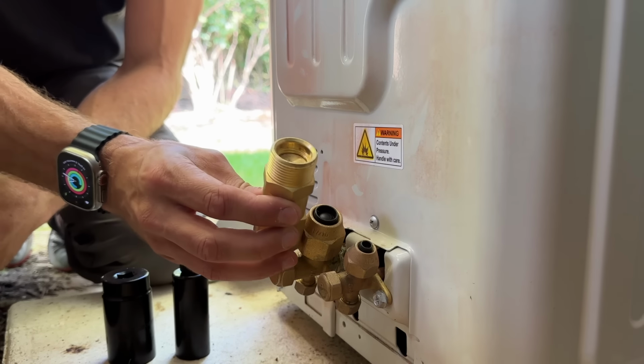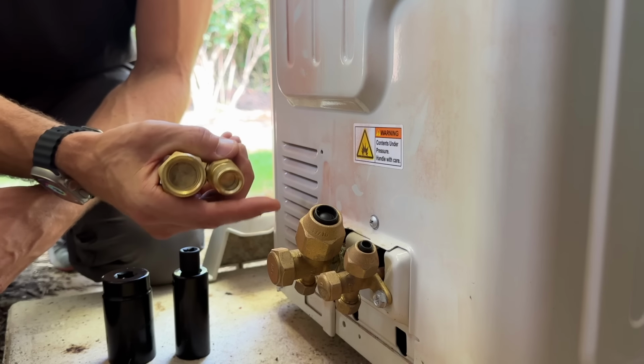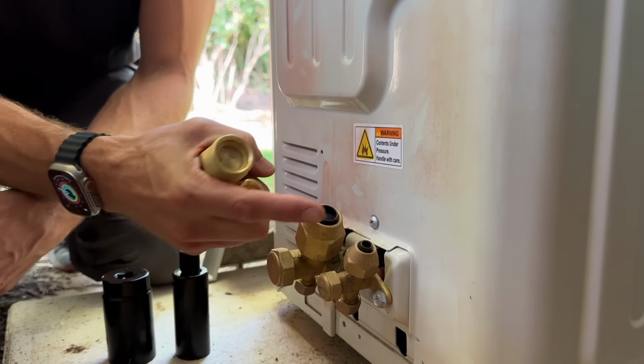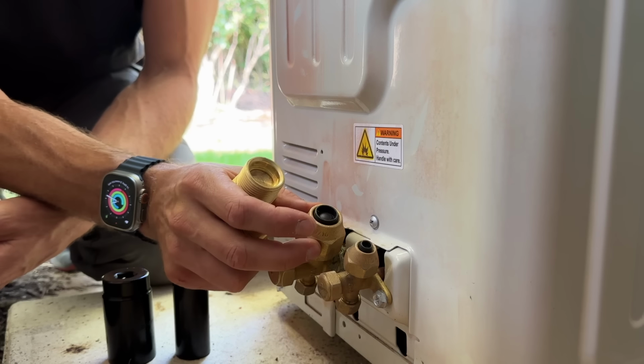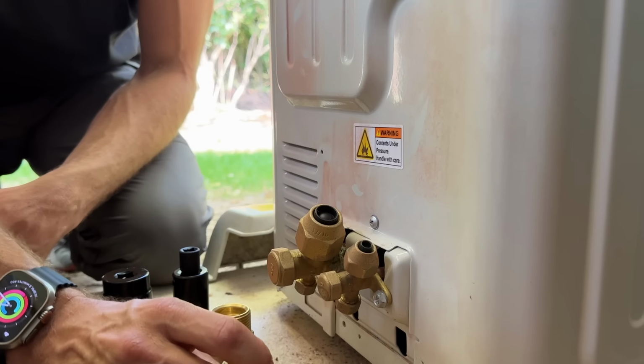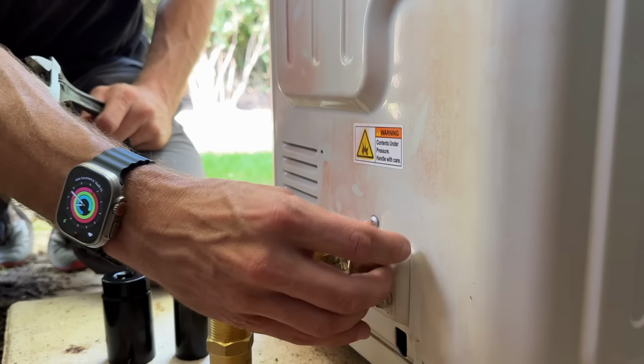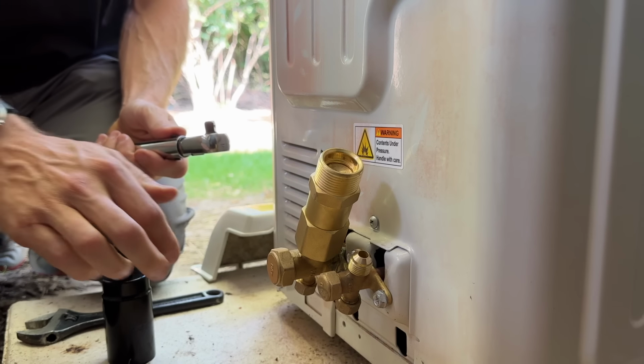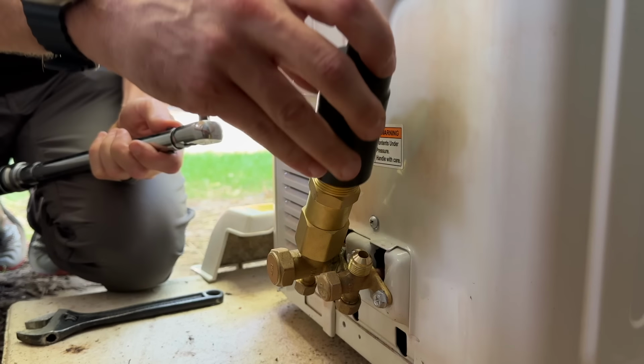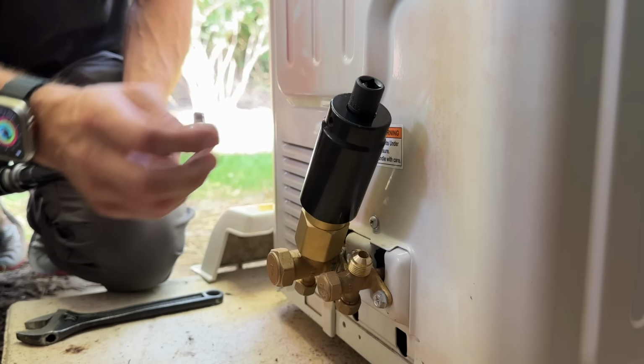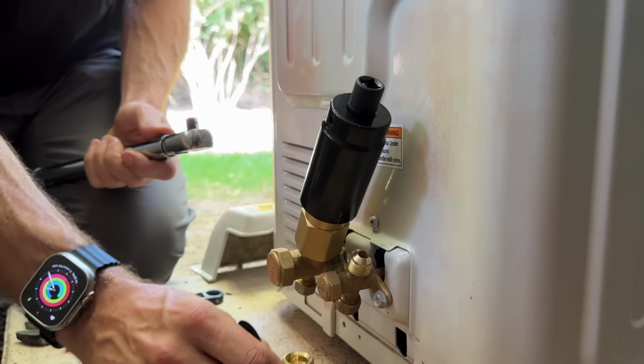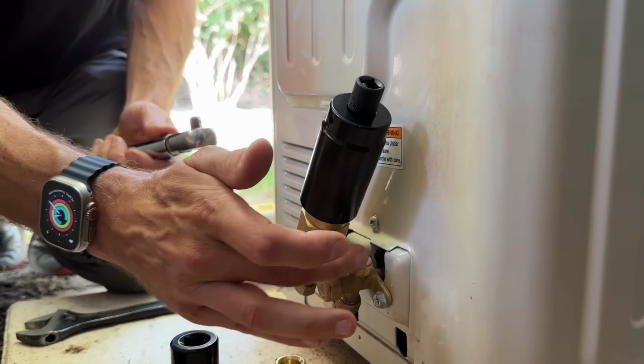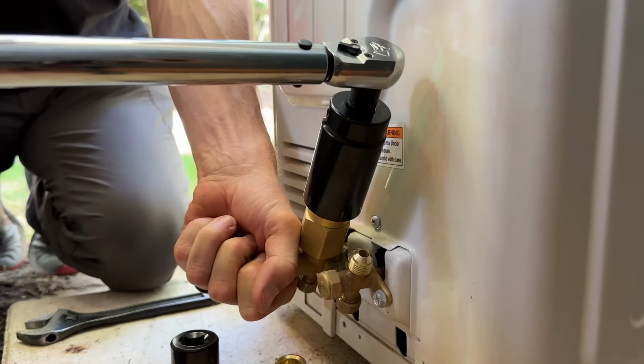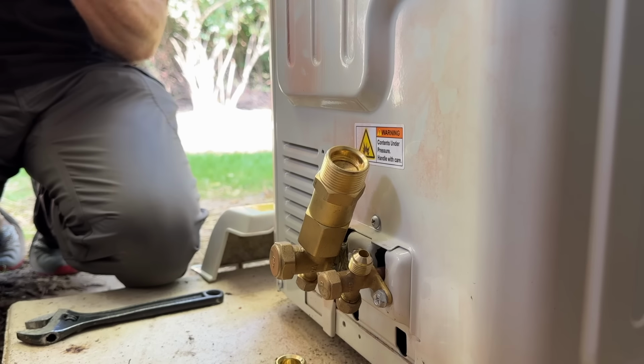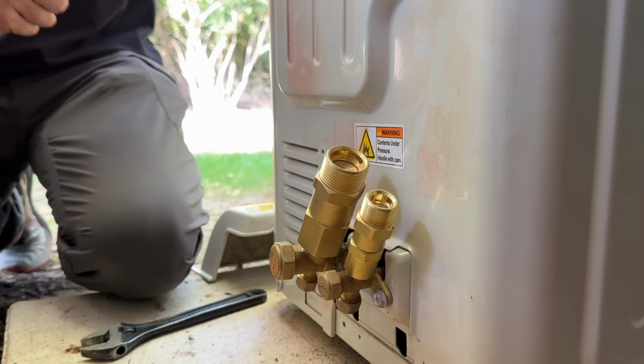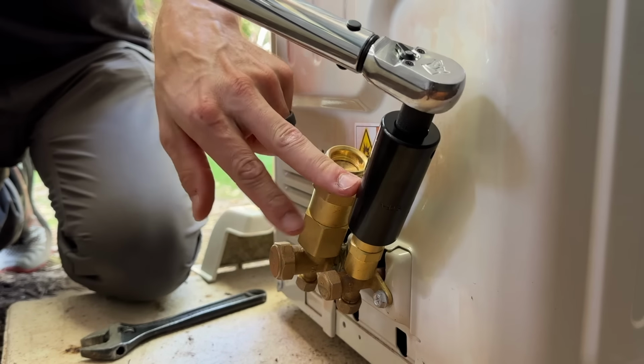All right, so next up we need to put these cutoff valves both at the outdoor unit and the indoor unit. We'll take off the caps here, and you are not gonna put any Teflon tape on these connections. They are made to seal as they are, so you do not need any pipe dope or Teflon tape. That can just cause you some issues. Now you will need to torque these down. For this cutoff, you're gonna need a 1.25" socket and a torque wrench, and then you're gonna torque this down to 70 Newton meters. And then for a smaller cutoff, you need a 7/8, and then we'll be torquing that down to 50 Newton meters. And then correction on the smaller one, instead of a 7/8, you're gonna need a 15/16 deep socket.